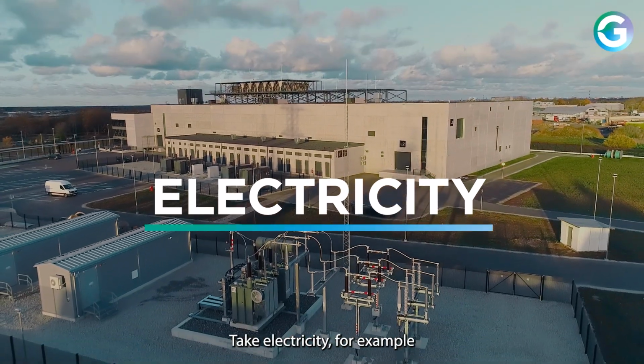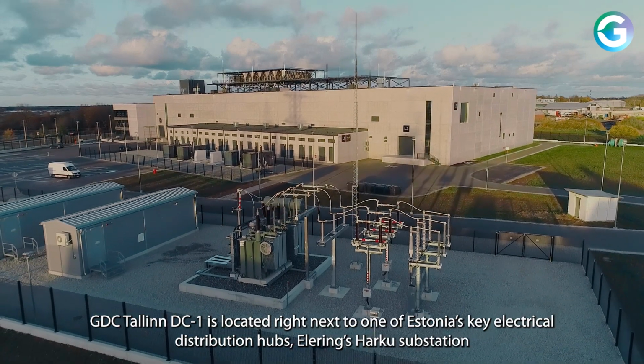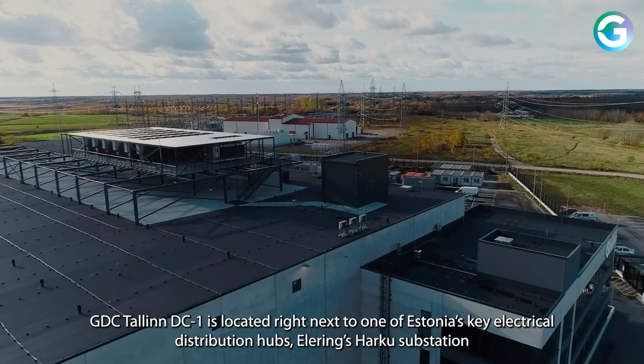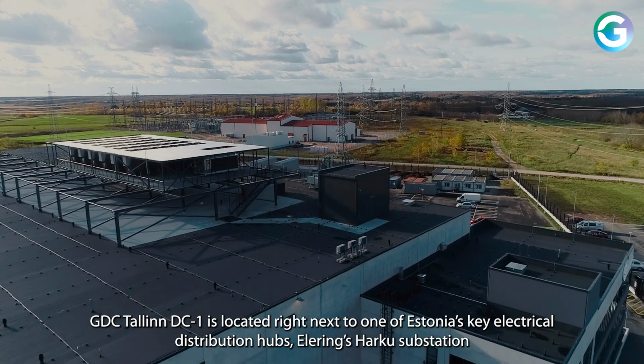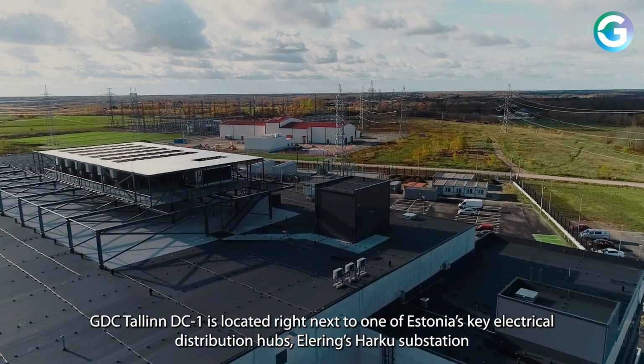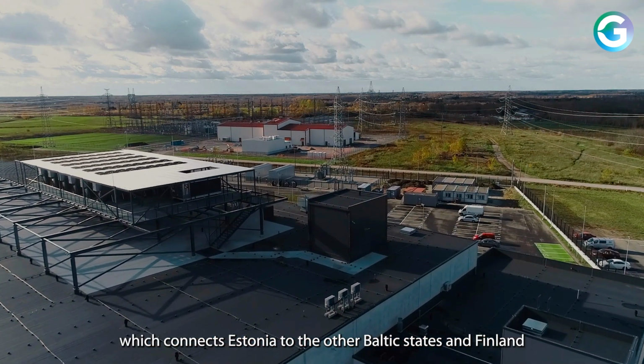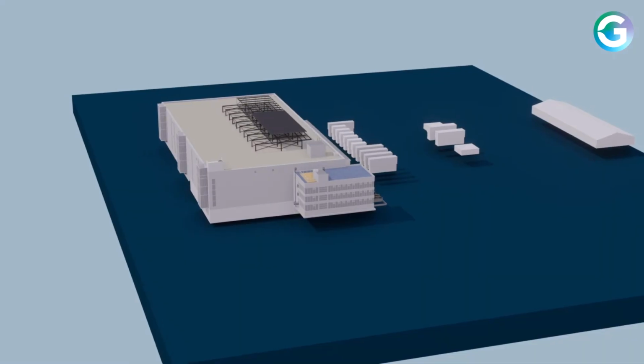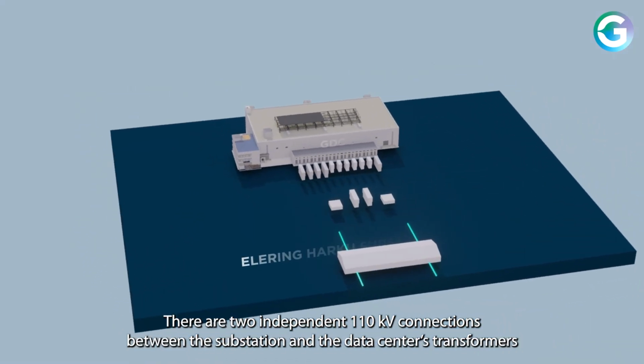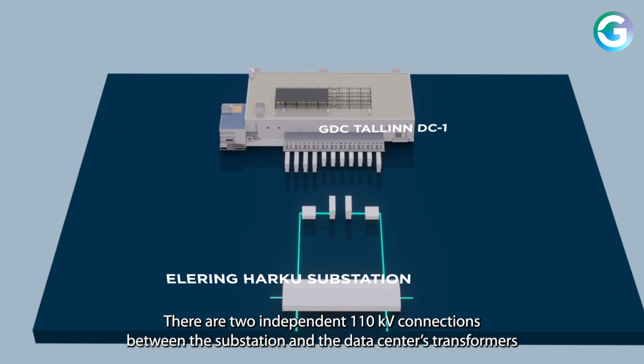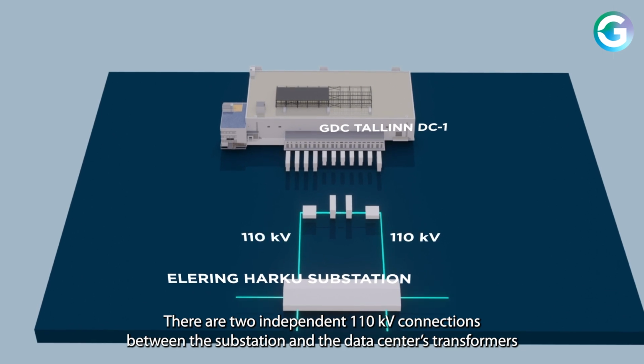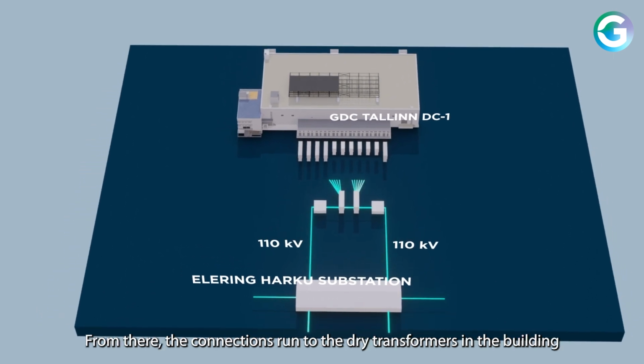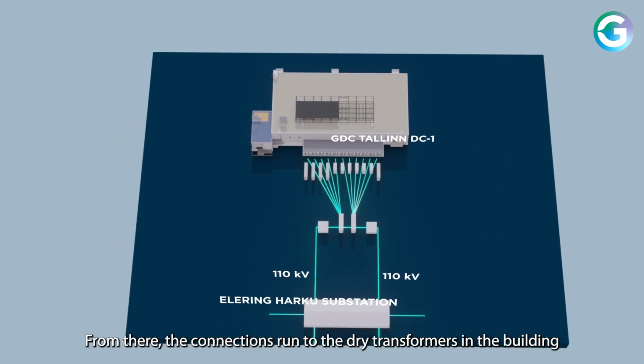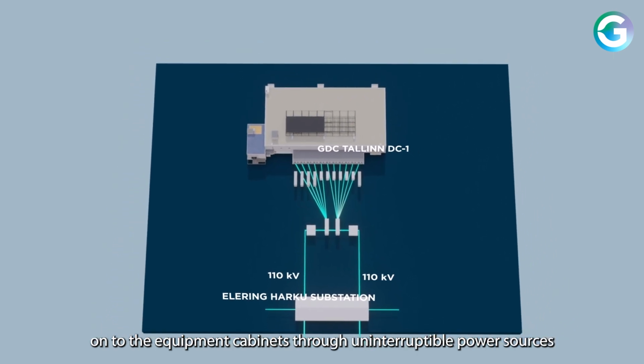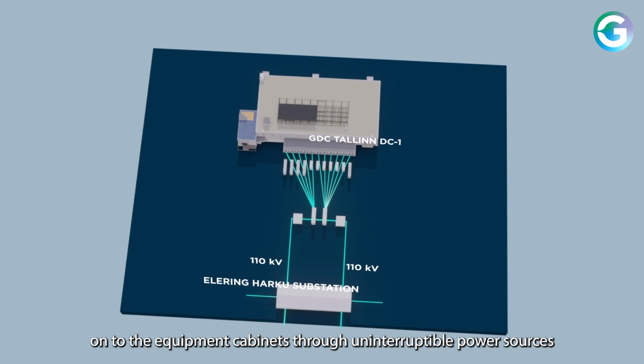Take electricity, for example. GDC Tallinn DC1 is located right next to one of Estonia's key electrical distribution hubs, Elering's Harku substation, which connects Estonia to the other Baltic states and Finland. There are 2 independent 110 kilovolt connections between the substation and the data center's transformers. From there, the connections run to the dry transformers in the building, onto the equipment cabinets through uninterruptible power sources.